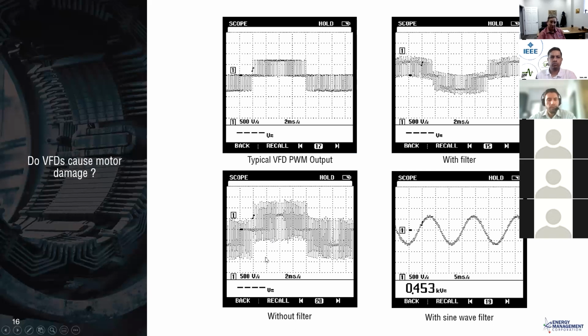And the customer originally called us because they had a motor failure. And because we do root cause analysis on machines, we were able to determine that that was an end-turn failure. That's a classic DVDT failure on that initial coil turn where the voltage potential is the highest. And it happened to be on an inverter duty motor, by the way.